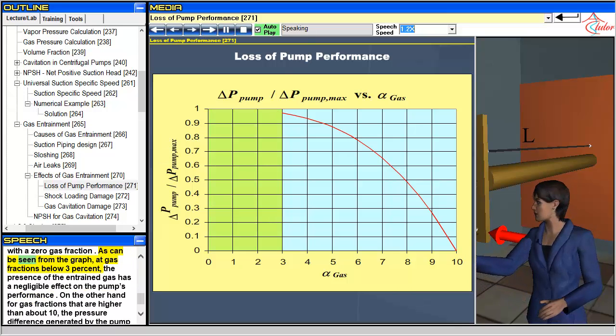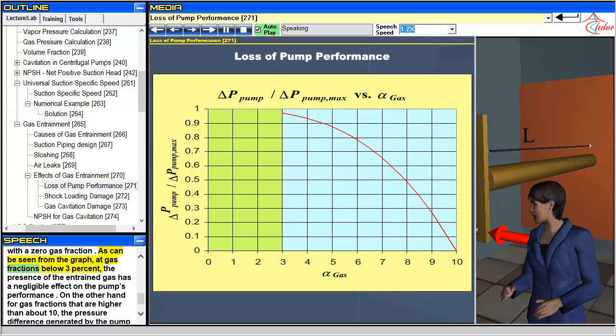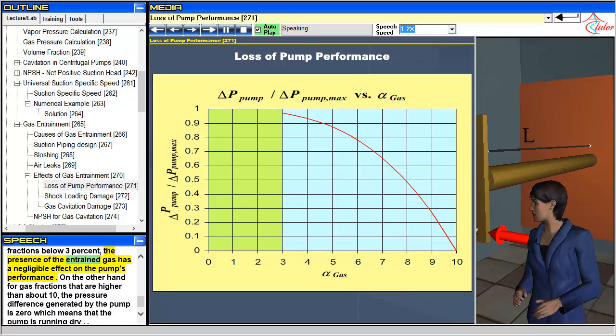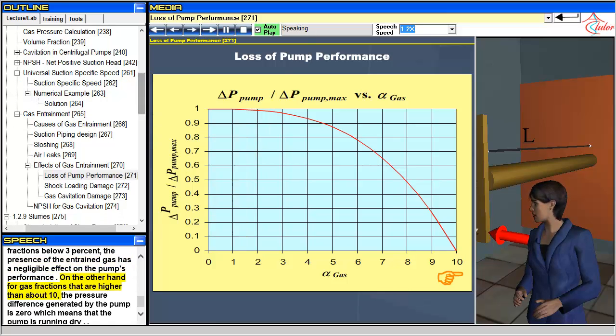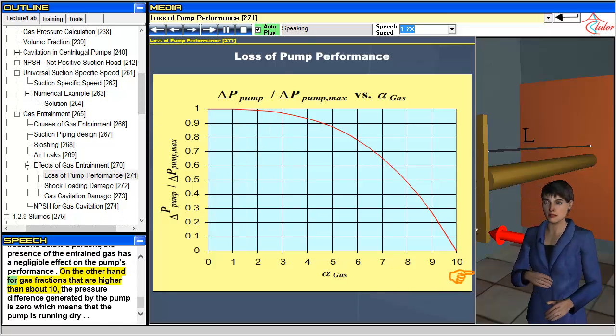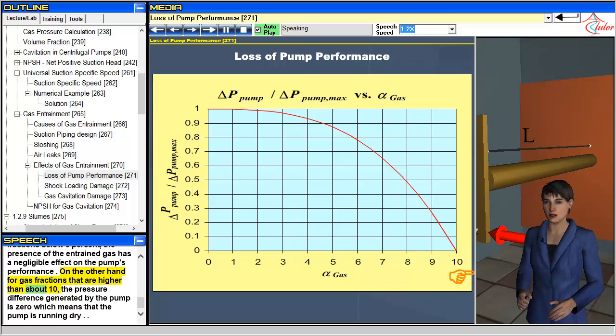As can be seen from the graph, at gas fractions below 3 percent, the presence of the entrained gas has a negligible effect on the pump's performance. On the other hand, for gas fractions that are higher than about 10 percent, the pressure difference generated by the pump is zero, which means that the pump is running dry.